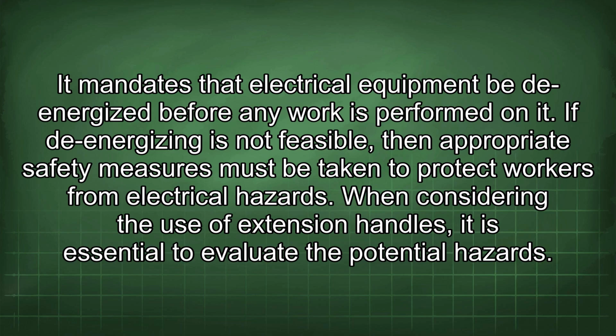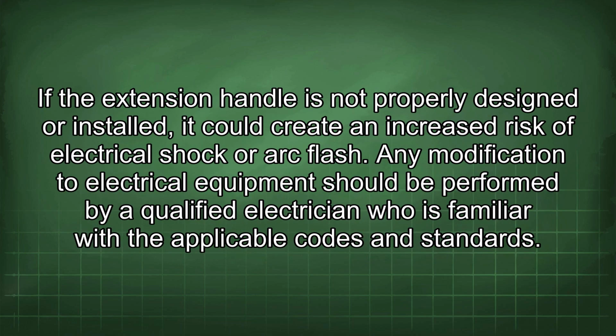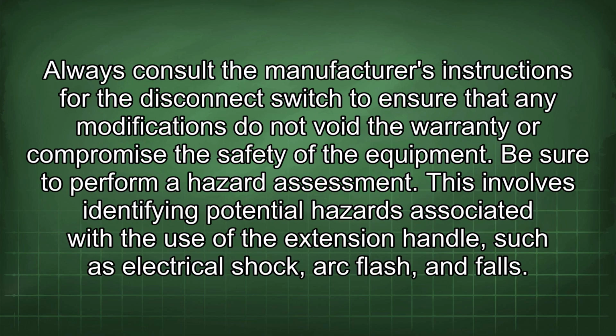When considering the use of extension handles, it is essential to evaluate the potential hazards. If the extension handle is not properly designed or installed, it could create an increased risk of electrical shock or arc flash. Any modification to electrical equipment should be performed by a qualified electrician who is familiar with the applicable codes and standards. Always consult the manufacturer's instructions for the disconnect switch to ensure that any modifications do not void the warranty or compromise the safety of the equipment.